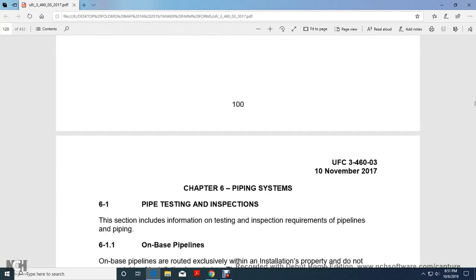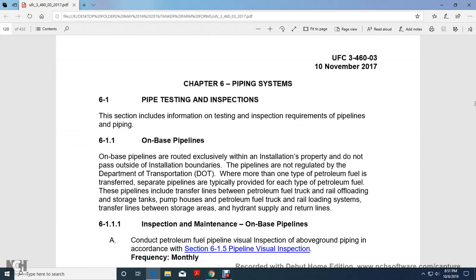All right, Chapter 6, Piping Systems. Piping system testing and inspection. These sections include the information for the testing and inspection requirements of the pipeline. On-base pipeline is routed exclusively within the installation property and does not pass outside of the installation boundaries. Pipelines are not regulated by the Department of Transportation when more than one type of petroleum fuel is in transfer. Separate pipelines are typically provided for each type of petroleum fuel.